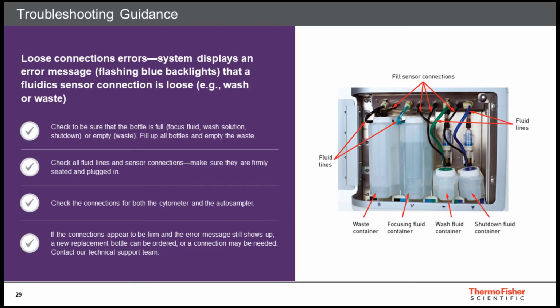Loose connections of the fluidic lines can result in a multitude of issues, so always ensure the fluidic lines from the containers and the sensor cables are connected properly. A waste line not connected properly will result in a clogged message, as the path to the waste is obstructed, resulting in back pressure in the system, which the Attune NxT interprets as a clog.